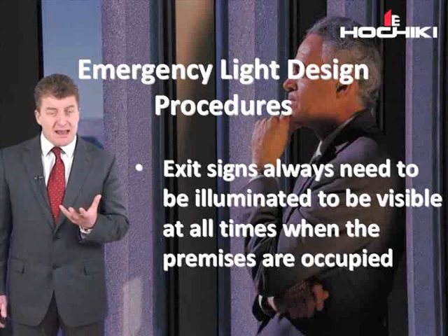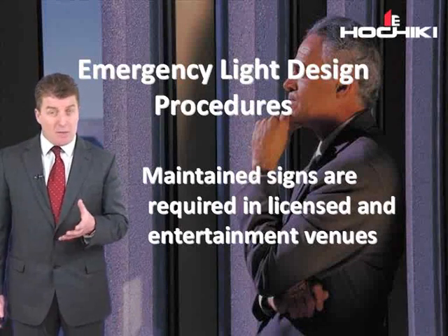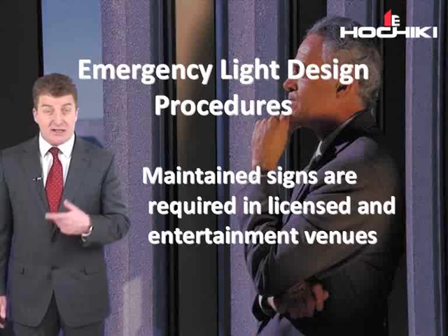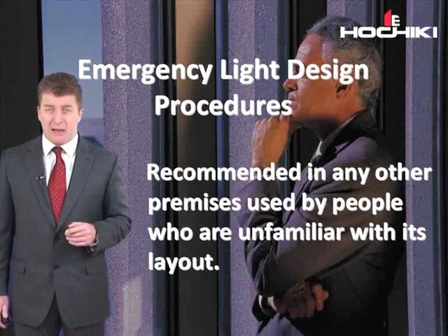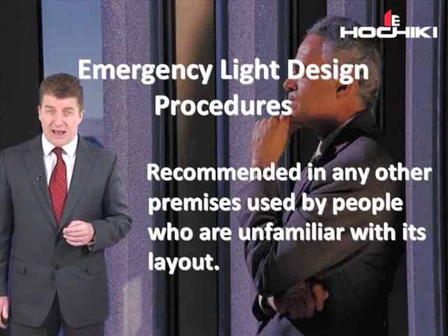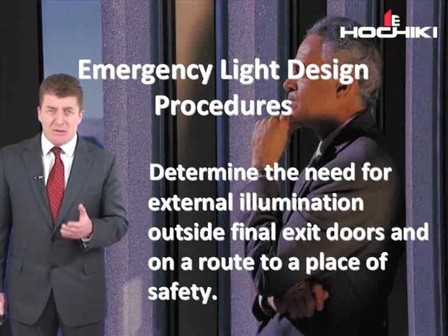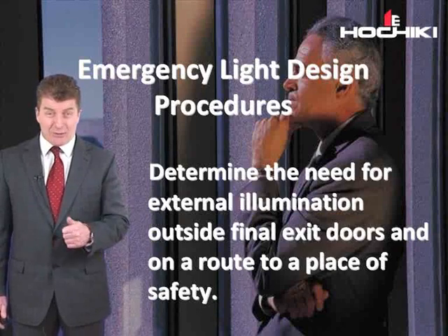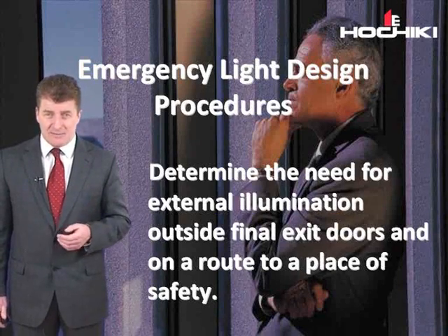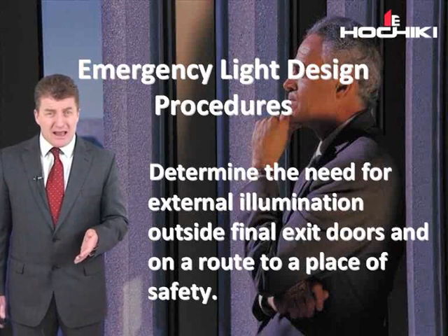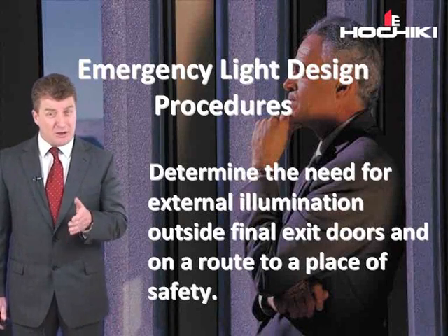Then you're looking at whether it's maintained or non-maintained signs. Maintained signs are required in licensed and entertainment venues and are recommended in any other premises used by people who are unfamiliar with its layout. Then you've got to determine the need for external illumination outside the final exit doors and on a route to a place of safety. Other areas that need illumination, although not part of the escape route, should be located.